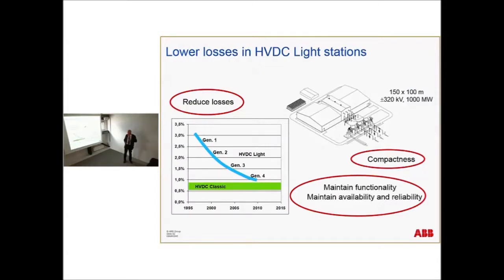And from the beginning, we had rather high losses in the HVDC light stations. We had about 3% per station. But today, with the new generations, we are down to 1% losses in the stations. Then you have to add the cable losses or overhead line losses, of course. But still, losses are today so low that you will have lower losses than for an AC system. And it's compact, and we maintain the functionality and availability and reliability.